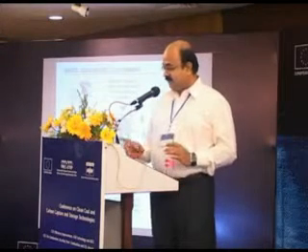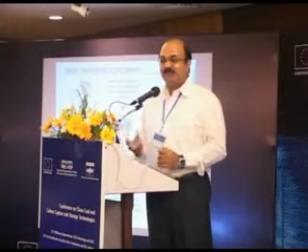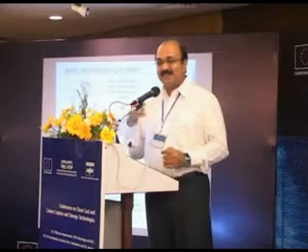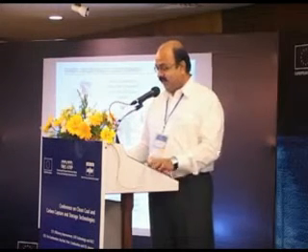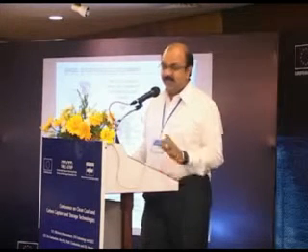By changing the ESP electronics alone, was there any improvement in particular? I think in this case they replaced the TR sets and all the internals. I would say most of the ESP is replaced. What will you keep in an ESP, sir? Probably some portion of the hopper and things like that. Rest all has to be totally replaced. But yes, it comes with the advancement in electronics. I don't remember whether the power management system was added in this case. I have to check, since we didn't do that directly ourselves. But maybe they added some power optimization systems to reduce the power consumption. Yes, I think so, because that's why we could finally reduce the power consumption.